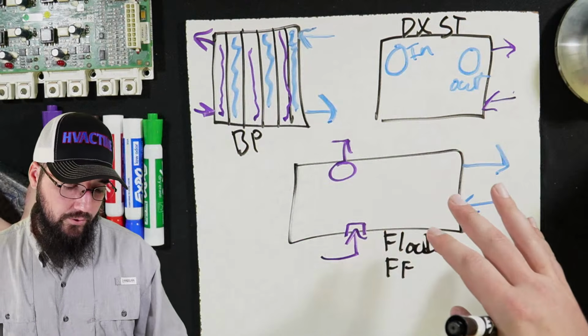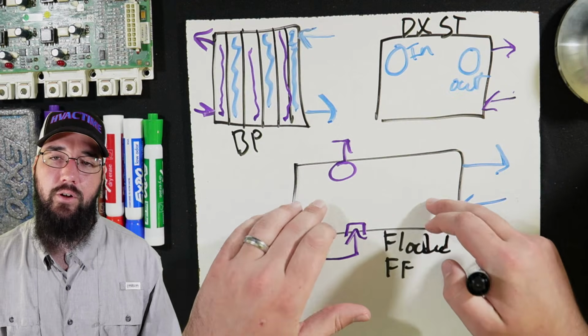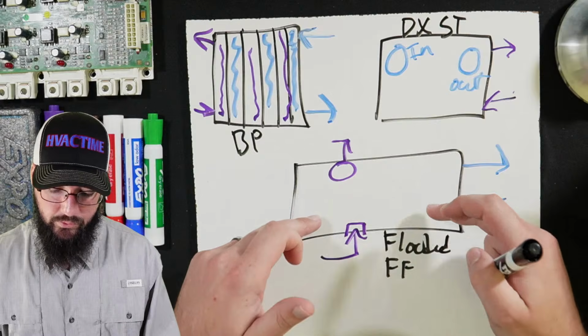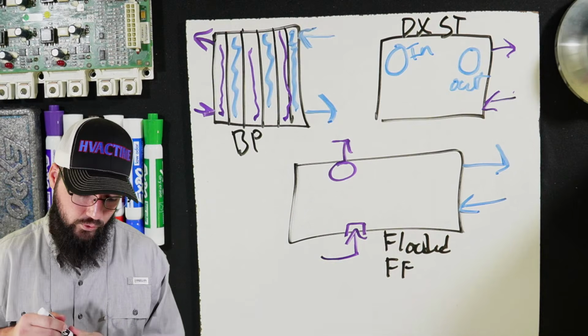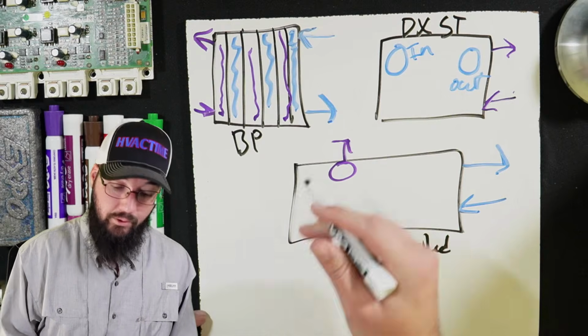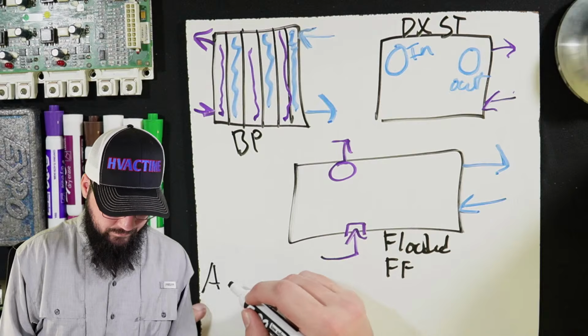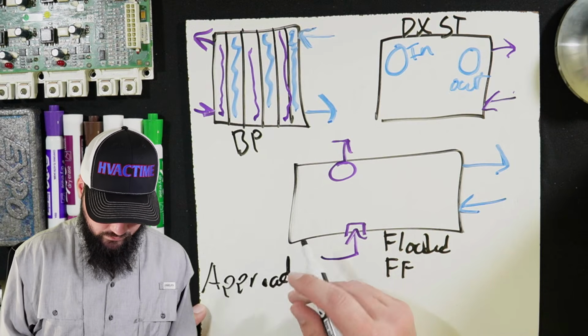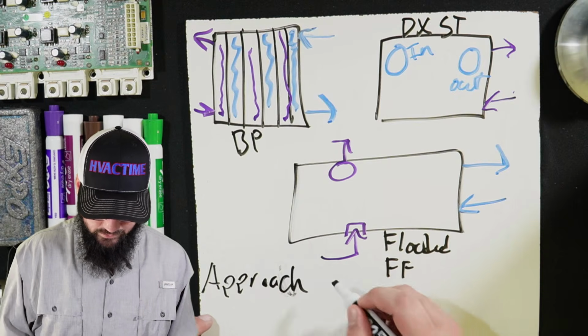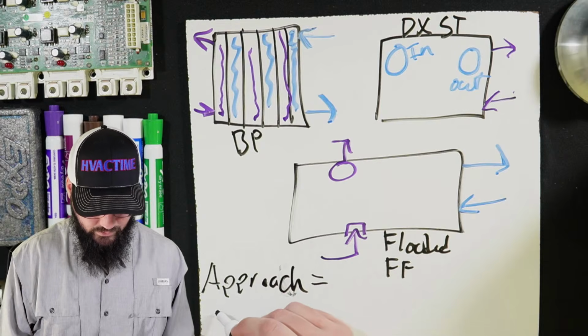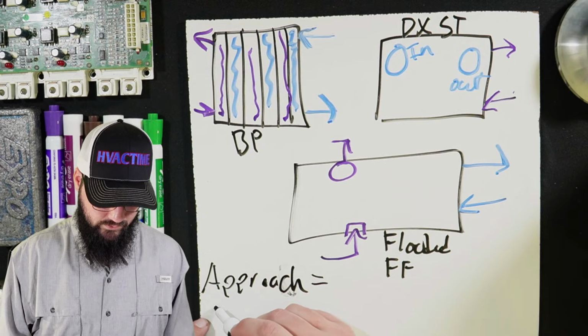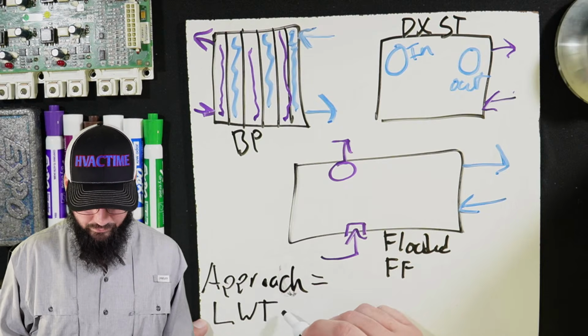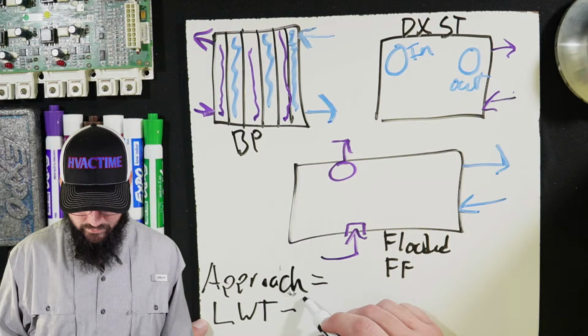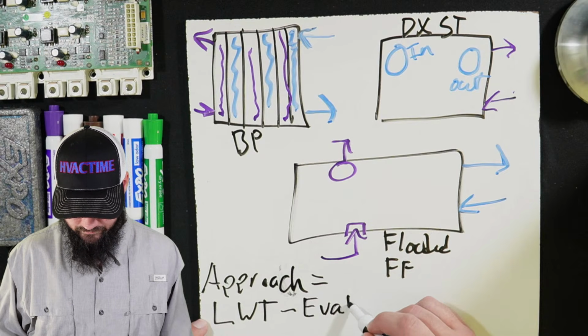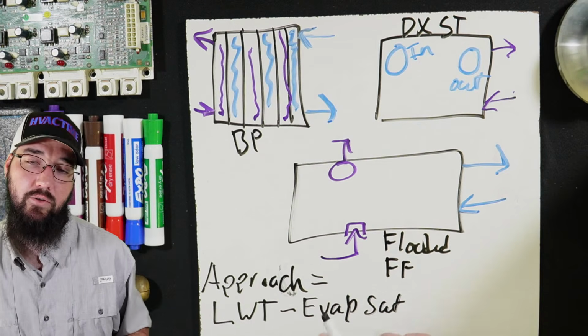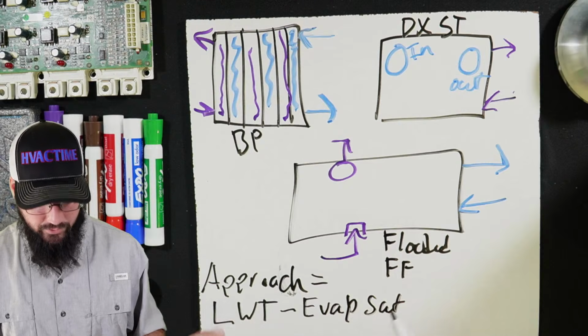All right, so other than why we have differences, these are the most efficient. We're going to get the most effectiveness out of our refrigerant by using these, and that's part of what we're measuring with approach. So approach, refrigerant approach, or evaporator approach, we'll say it that way. Approach equals the leaving water temp from the evaporator minus evap sat. By sat, I mean saturation, evaporator saturation. Subtract these two from each other, you get approach.